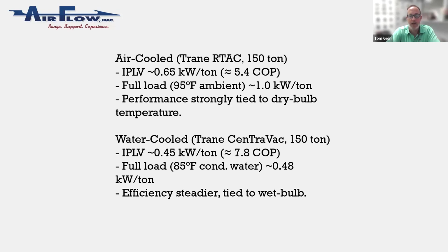So I said, okay, let's use Milwaukee and a 150-ton constant load. Will you ever have 150 tons constant load year round in Wisconsin? You will not, because you could use an economizer and your load isn't going to be continuous. But if we're running these things all year round, how do they shape up?